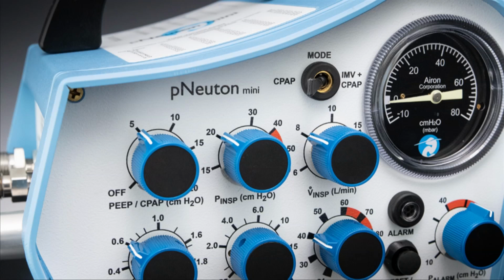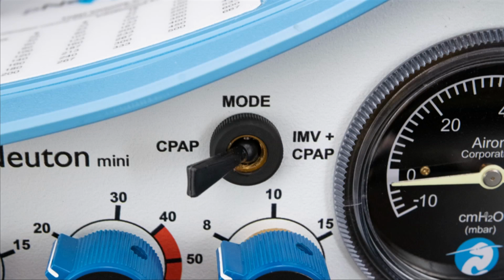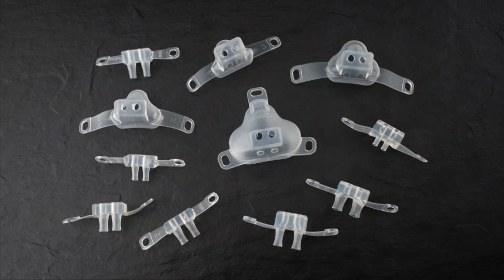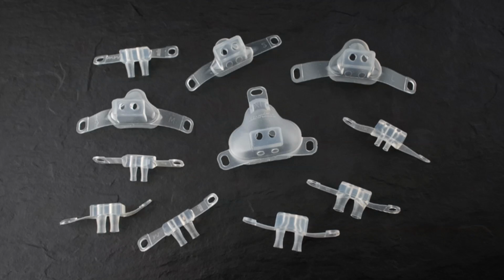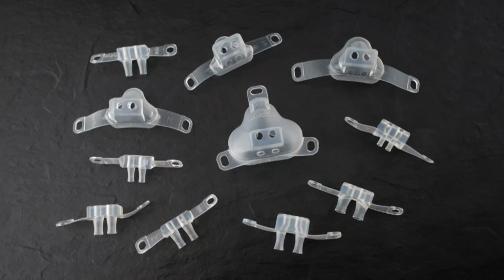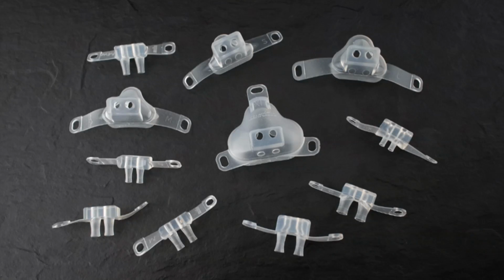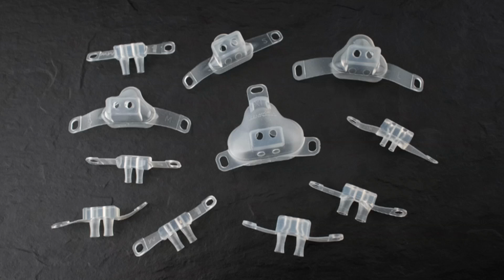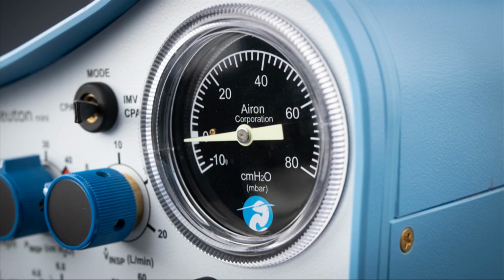The PEEP CPAP control can be set for baseline pressure for ventilation modes, with or without PEEP. The CPAP mode provides continuous flow based on the selection of the continuous flow control and CPAP pressure for spontaneous breathing patients. The pNeuton mini can deliver non-invasive CPAP with nasal prongs available in 7 sizes or a nasal mask available in 4 sizes. Manometer pressure gauge.